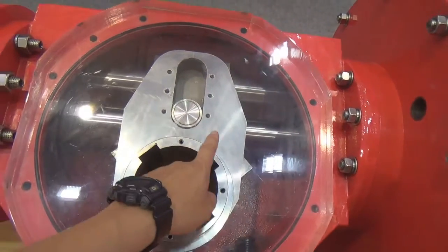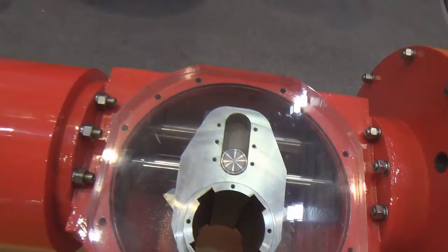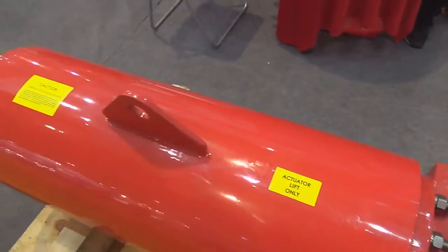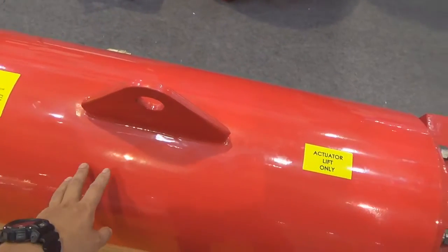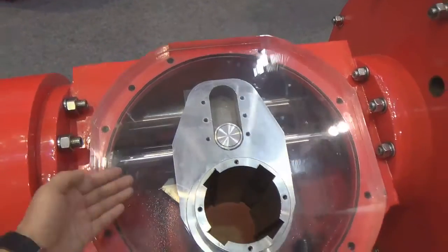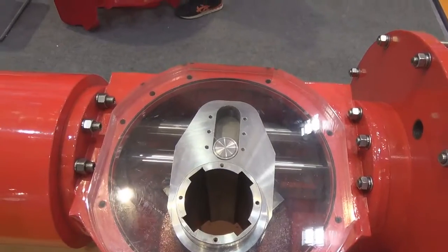The downside rod is going to push the yoke, and the yoke is going to turn, so we can open the valve. And when the cylinder loses the gas, this cylinder has a very big spring inside. The spring will push the downside rod and put the yoke back, so the valve will turn to another position.